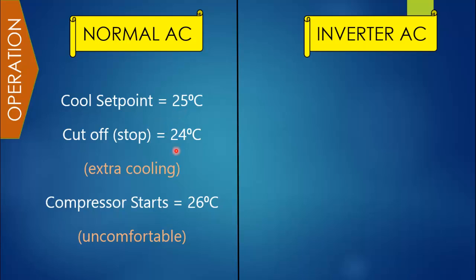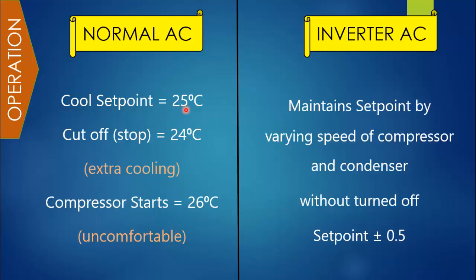So how does a normal AC operate? Let's say the cooling setpoint is 25°C. When it cools the room to 24°C it will cut off, and then the outdoor unit will start again at 26°C. You can see that first it provides extra cooling, then it shuts down and restarts at 26°C — so this temperature will again be uncomfortable, since the set temperature is 25°C.